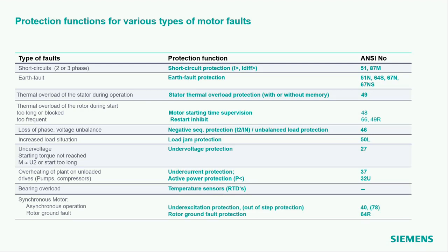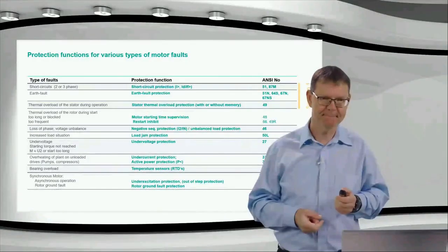Then for the synchronous motor, I have additionally the problem that the synchronous motor is not synchronous anymore, but falls into an asynchronous state or slows down. Therefore, we have the under-excitation protection and optionally the out-of-step protection. And often the rotor ground fault protection is also used.